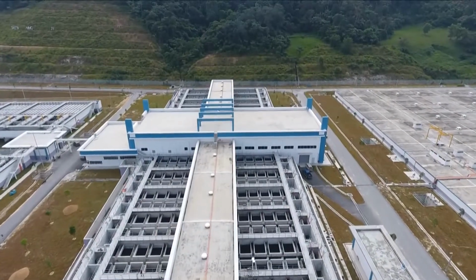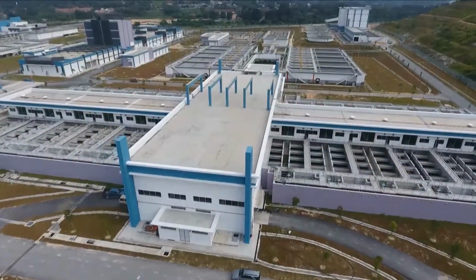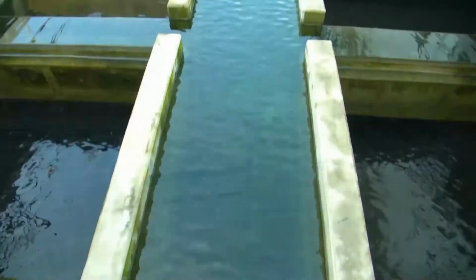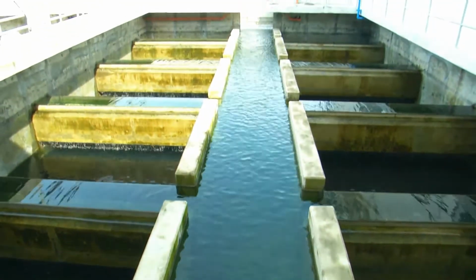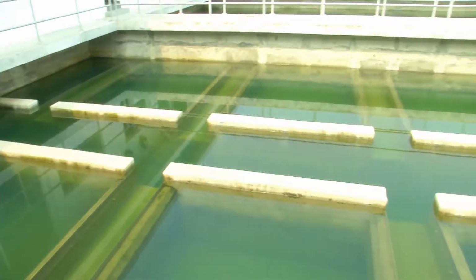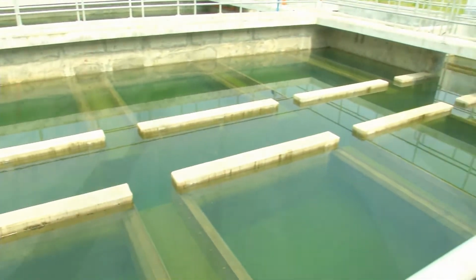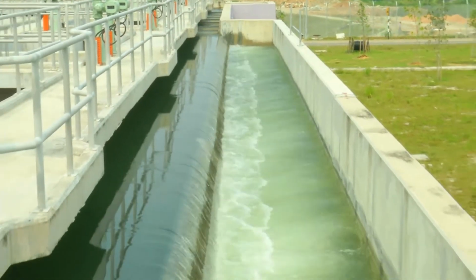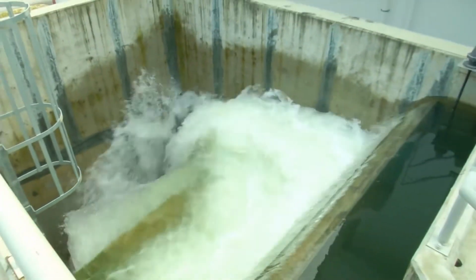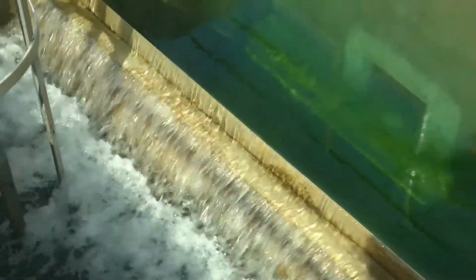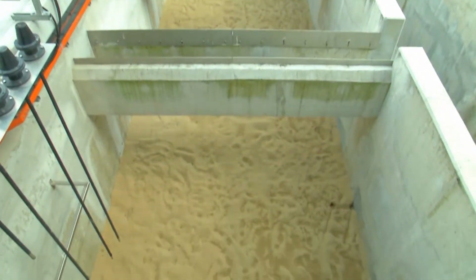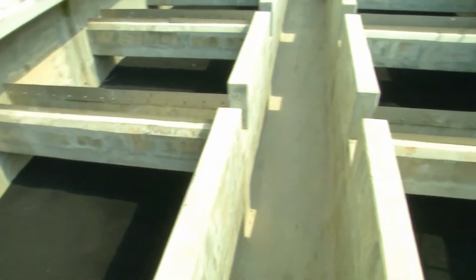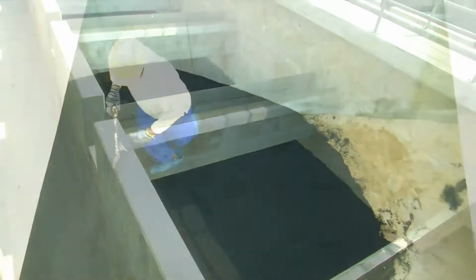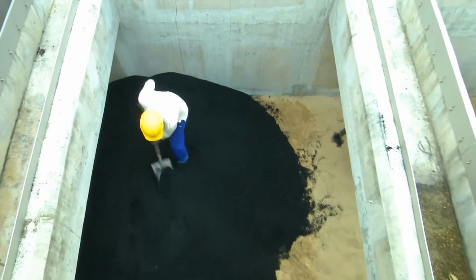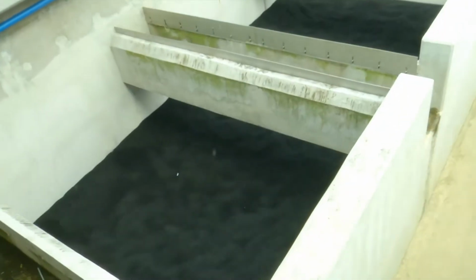Filtration plant. Besides the clarification plant, the filtration process is also a key treatment process in the water treatment plant. Rapid gravity dual media filters are constructed for this plant. The filtration plant is the downflow open gravity, constant flow, constant head type. Filter media used in this plant are sand and granular activated carbon for the removal of minute flocs carried over from the clarifiers and removal of taste and odor.